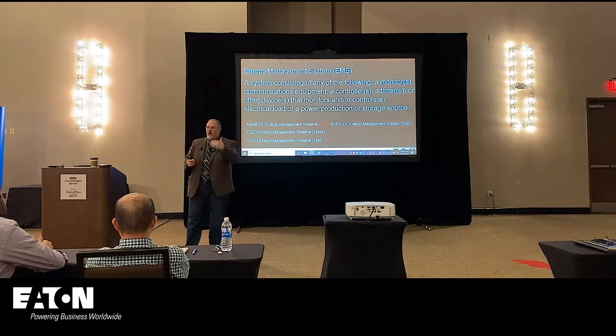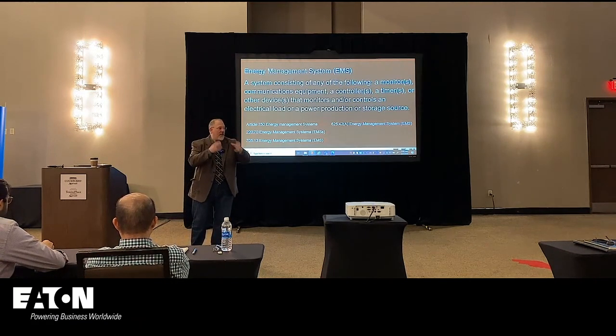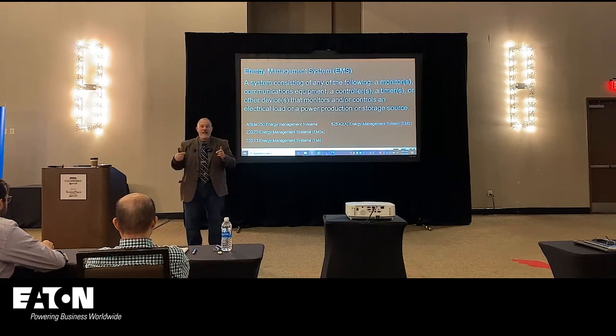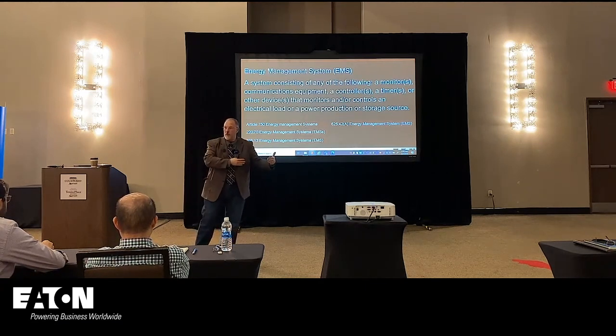And what do I have to do to the bus? I've got to consider now I have two sources, and I can put more load on this panel board, right? If my panel board's rated for 200 amps, and I have a 200 amp main, I can tell you I'm not going to get more than 200 amps long enough for me to overload and heat up that bus bar, right? But if I have my main at 200 amps and I have a photovoltaic system connected in, now I can put more than 200 amps worth of load and not trip an overcurrent device, and now my bus is overloaded.